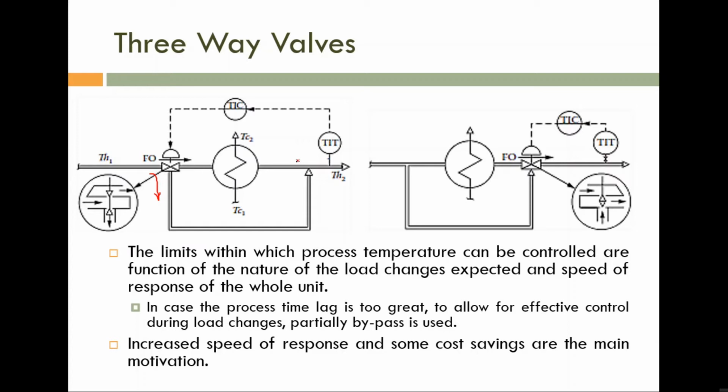So this path is fail open, which means by decreasing this control signal, we open this path so that more liquid is allowed to pass through the cooler and the temperature is decreased. More liquid through this cooler means less liquid through this bypass line. Am I correct?